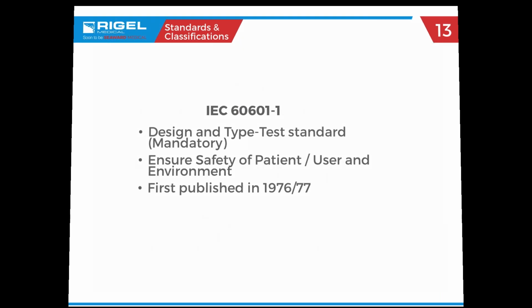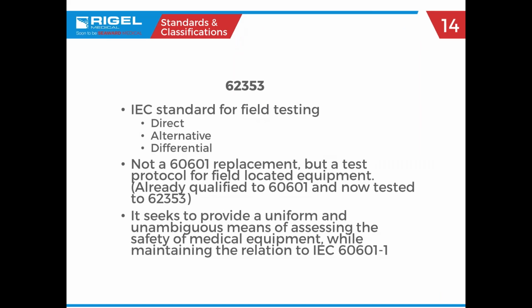So with the 62353, there are going to be 3 different versions of this: first direct, and then alternative and differential. The direct method is basically designed to test the same way as the 60601 standards, really no differences. The alternative basically says to connect your hot and neutral lines coming into the device and look at what the leakage current would be at the low voltages. And then finally differential, which, as its name states, is the differential between your hot and neutral lines.